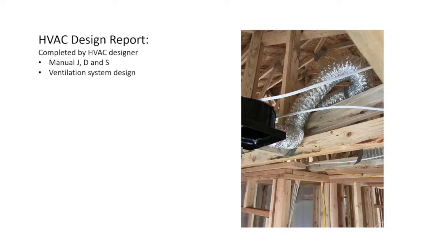So the design report. Before an HVAC system can be installed in a house, it needs to be determined how large that system is, and you do that by doing heat loss calculations, which for some reason is called a Manual J.